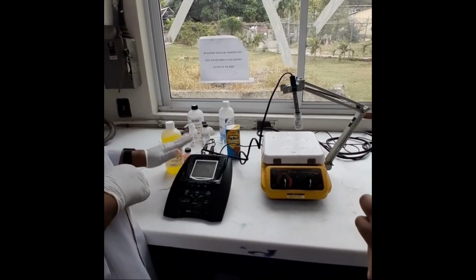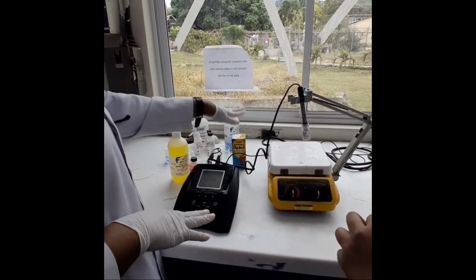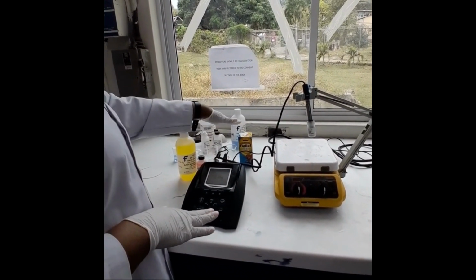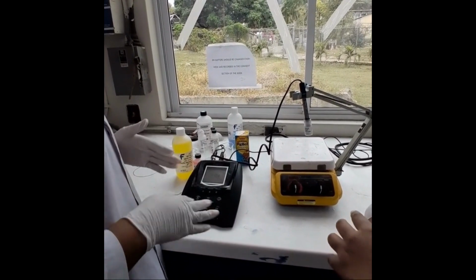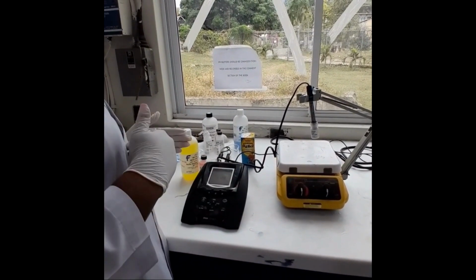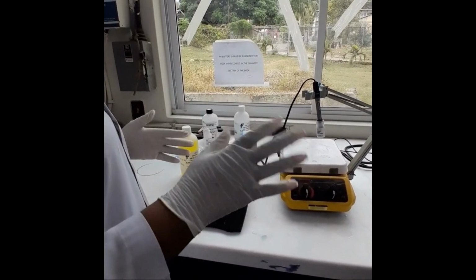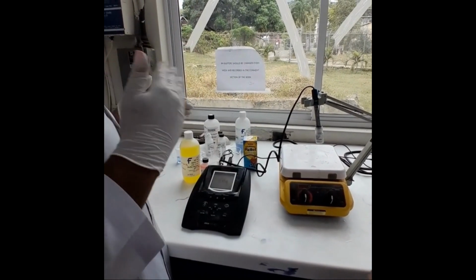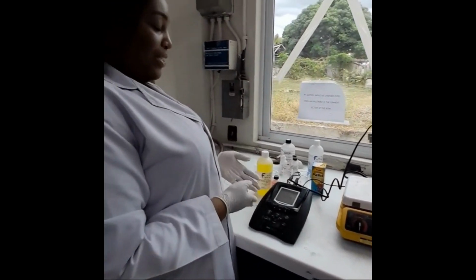All right. So we're choosing buffer 4 and 7. Why are we choosing buffer 4 and 7? Because the sample I'm working with today has a pH between 4 and 7. If you're doing a solution that has a pH higher than 7, you would use buffer 10. So you have to choose the buffers based on your expected sample.